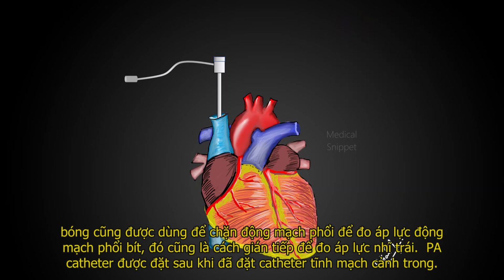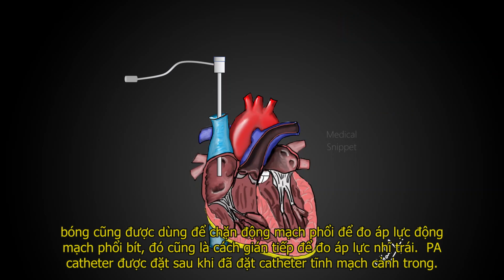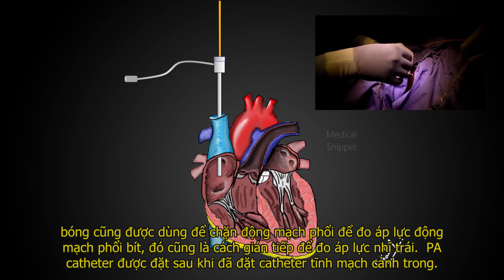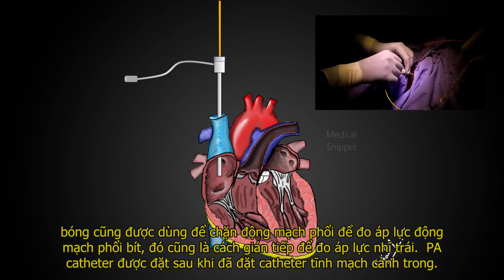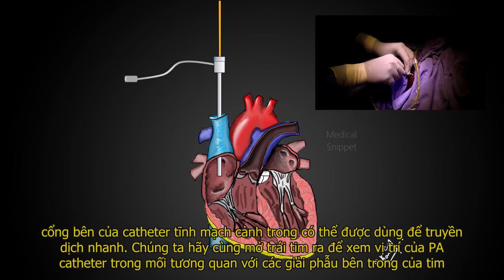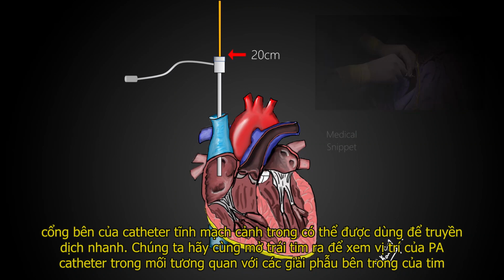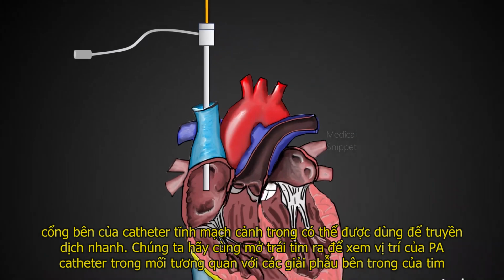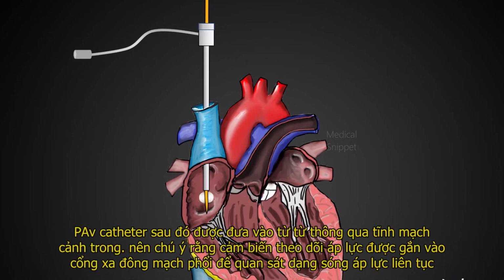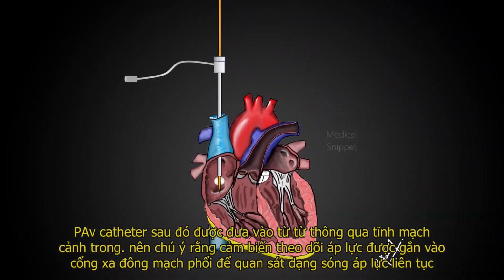Let's open up the heart to see the position of the PA catheter, in relation to the internal anatomy of the heart. Pulmonary artery catheter is then gradually inserted into the sheath. It should be noted that a pressure monitoring transducer is attached to the distal pulmonary artery port, to observe the continuous pressure waveforms. Once the catheter is inserted till the 20 cm mark, it usually crosses the tip of the insertion sheath. Now the balloon of the catheter is inflated with 1.5 ml of air. So now the tip of the catheter floats in the blood, and aids in the correct placement of the catheter.